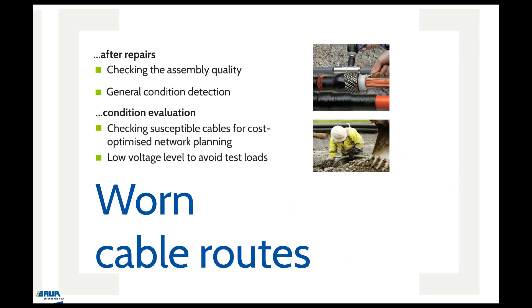A further field of application is testing and diagnostics on worn cables after repair. If a repair of a cable route was necessary, the assembly quality is checked after its completion to establish whether the repair was performed properly and the problem was rectified, or whether there are further faults on the cable route. At the same time, the general condition of the cable route is determined. When evaluating the condition of worn cables, the focus is on checking critical or susceptible cable routes. It is important to understand that the voltage level is deliberately kept low during condition evaluation with cable diagnostics to avoid test loads.